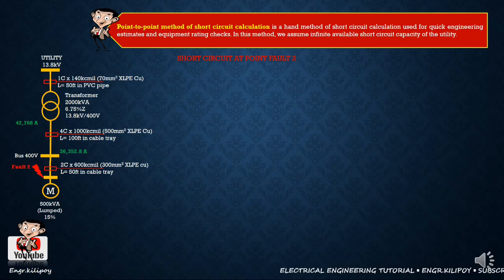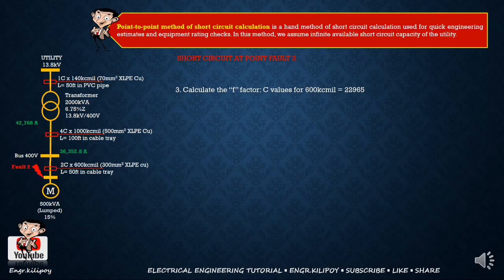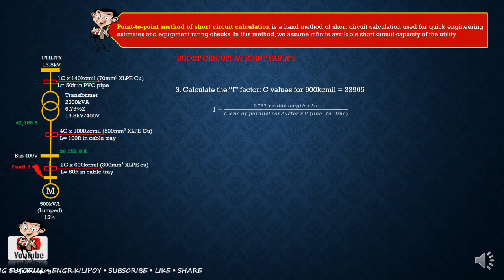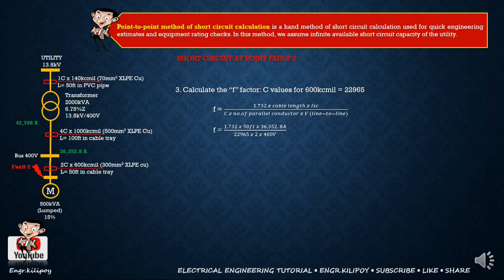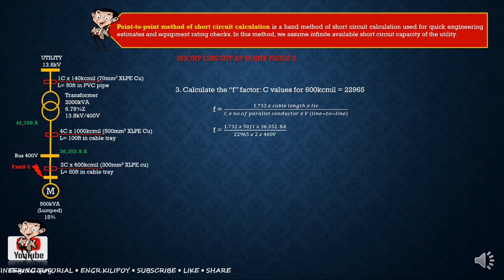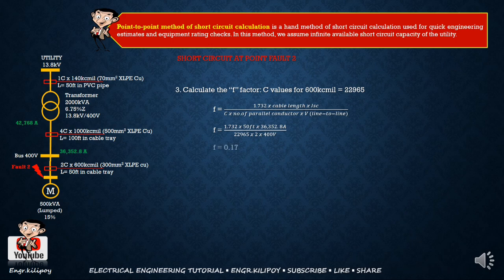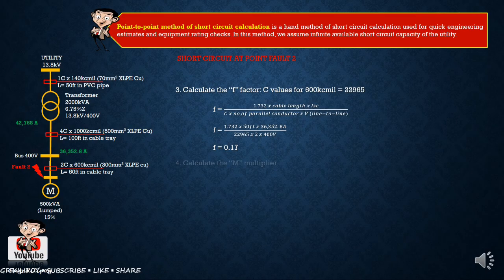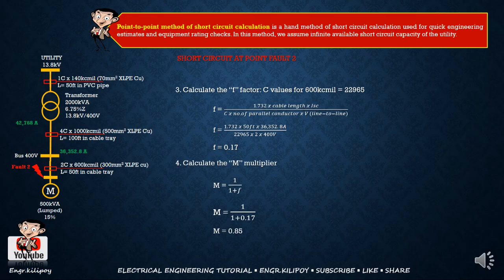So, short circuit calculation at fault 2 naman tayo. Again, kailangan nating i-calculate yung F factor using the formula. So, direct substitution lang naman yan. Yung C values ng 600 kcmil as per C factor table is 22,965. So, we have F value na 0.17. So, calculate the M multiplier. We have 0.85.